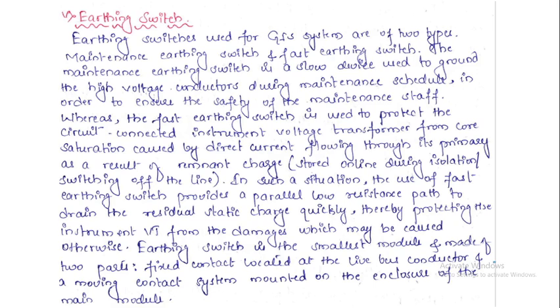Next we have the earthing switch. Earthing switches used for a GIS system are of two types: maintenance earthing switch and fast earthing switch. The name itself suggests that maintenance earthing switches are used for maintenance purposes. The maintenance earthing switch is a slow device used to ground the high voltage conductors during the maintenance schedule. In case of any repair, we need to isolate that part, and under that condition these earthing switches play a vital role.